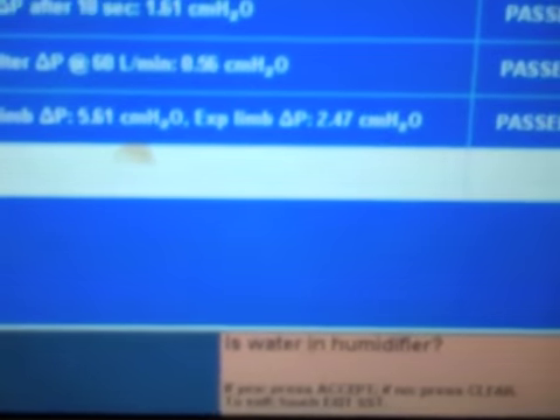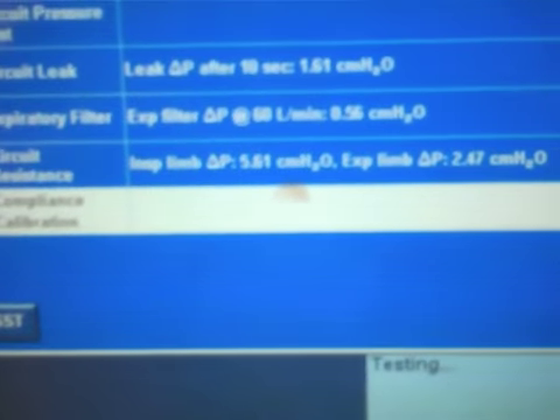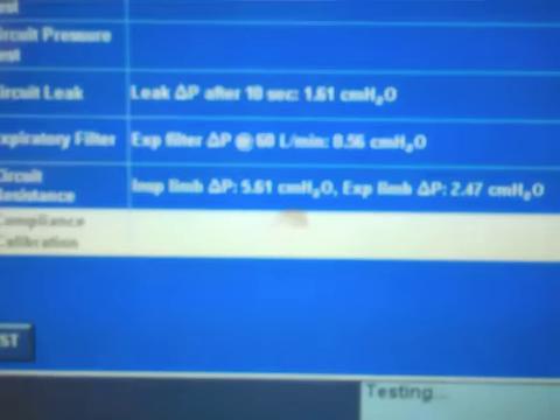It's asking, is there water in the humidifier? Well, that's going to change your dead space, so you can go ahead and select if water's in it. Mine's not. If yes, press accept. If no, press clear. So I'm going to press clear. Now it's doing the compliance calibration.